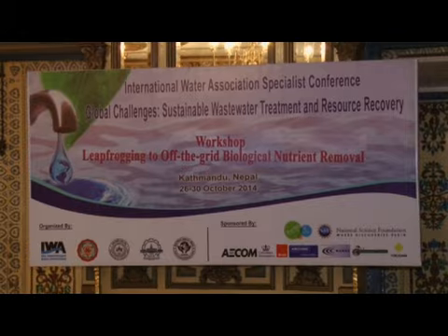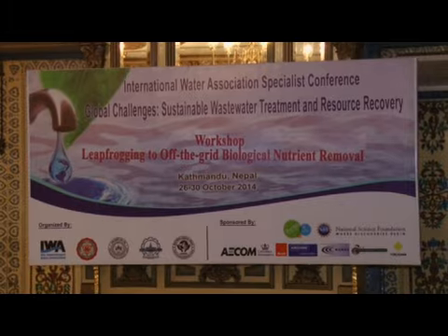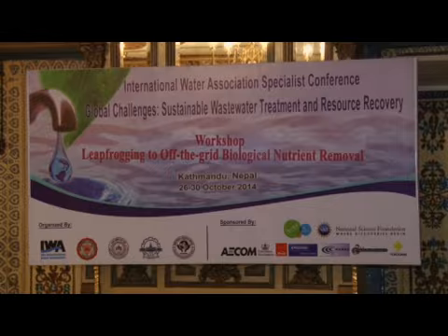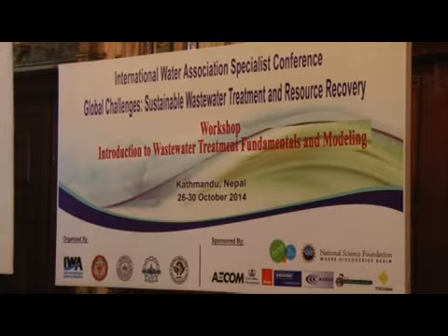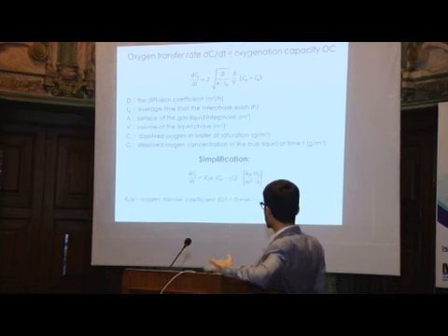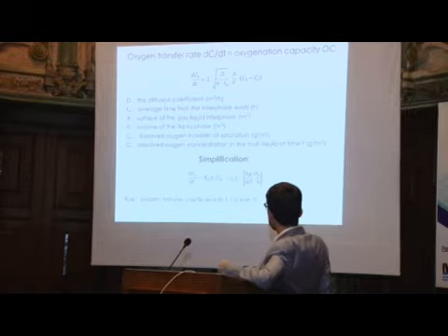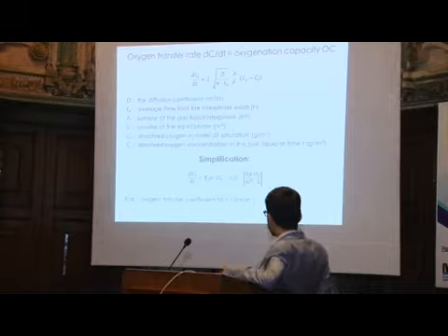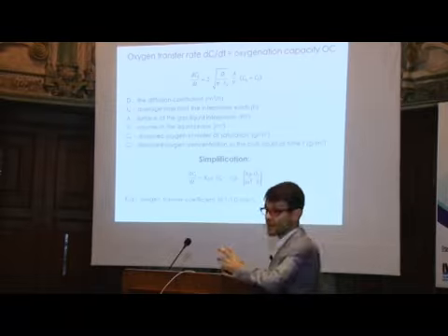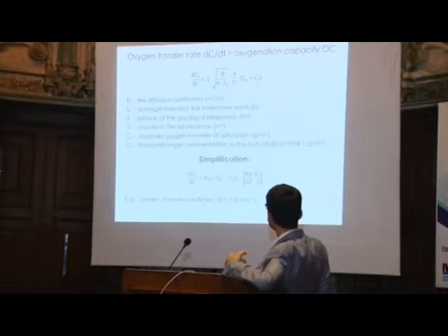So their design point, if you get the most efficient energy motor or generator and you operate it at 6. In Europe, typically we're between 10 and 20, but in different climates there are clearly a lot of parameters, but we can simplify it in this formula, which says the oxygen transfer rate equals the value KLA, and that is a lumped value. So there are many mechanisms behind. All of this is put in this KLA. We call it the oxygen transfer coefficient, expressed per time.